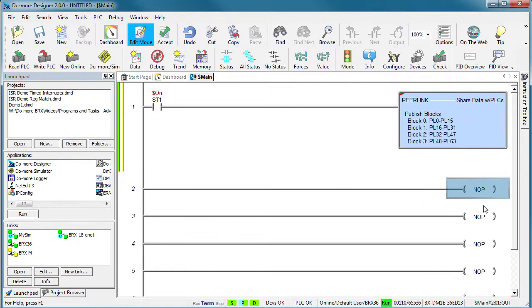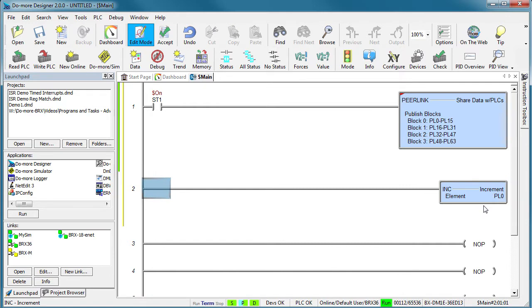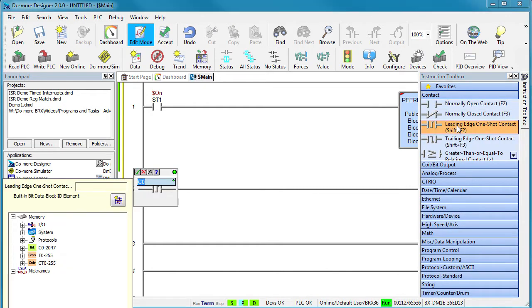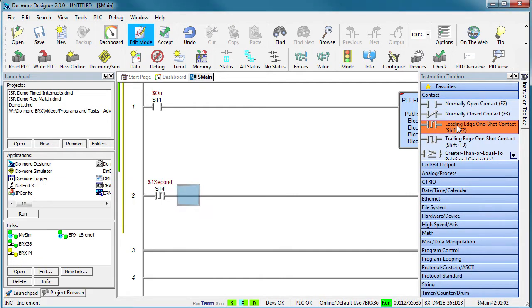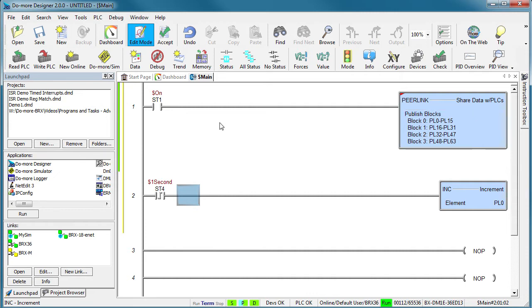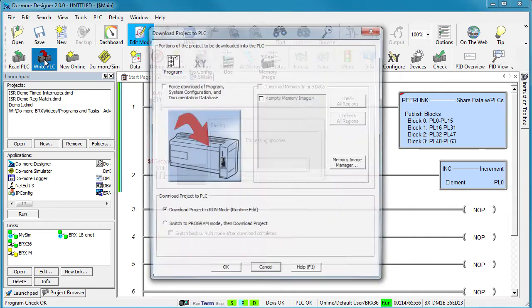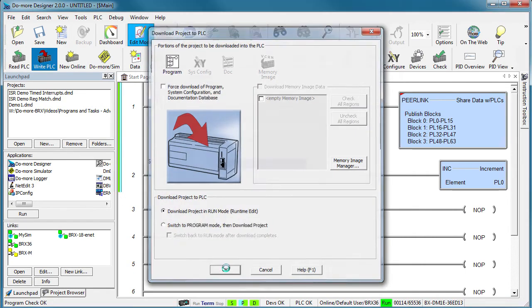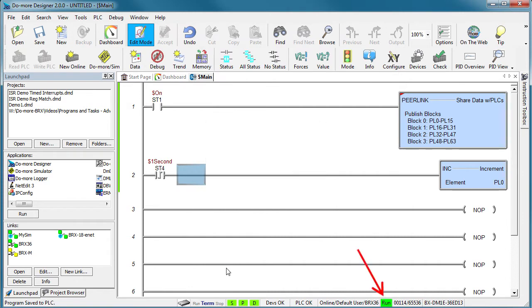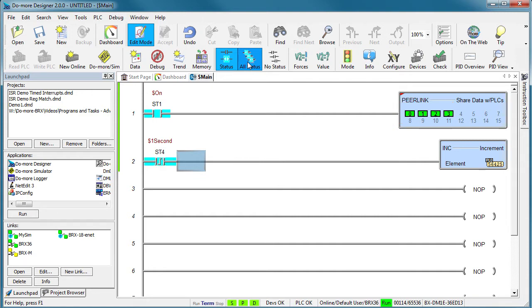Let's have this PLC increment PL0 once a second. Remember, we gave this PLC access to the first 4 blocks of Peerlink memory so it can write or publish data to locations 0 through 63. Accept our changes and write it out to the PLC. Make sure the PLC is in run mode and with status enabled we can see which blocks of the Peerlink memory space this PLC is publishing to and there's no activity on the other blocks. Great.